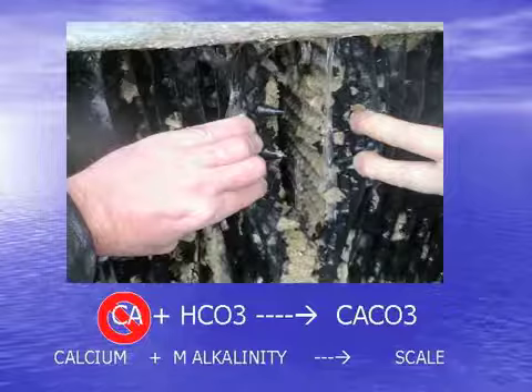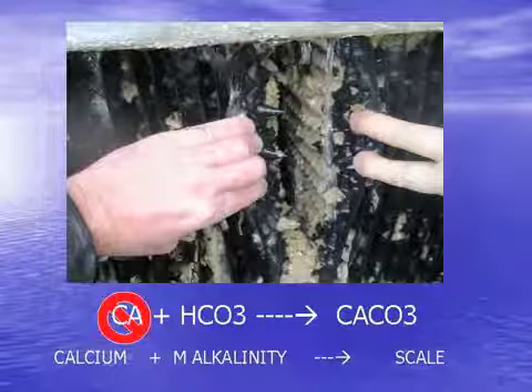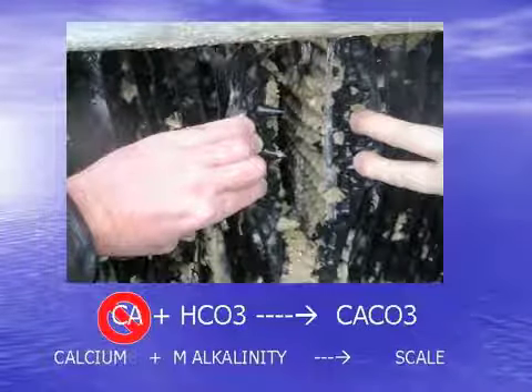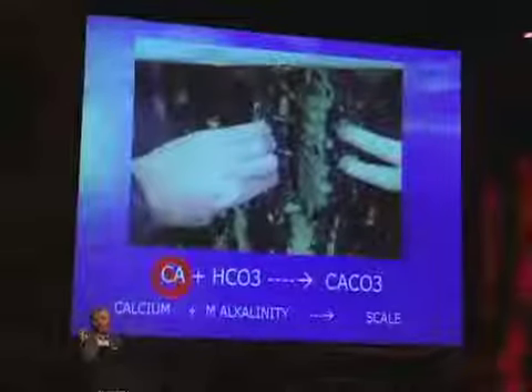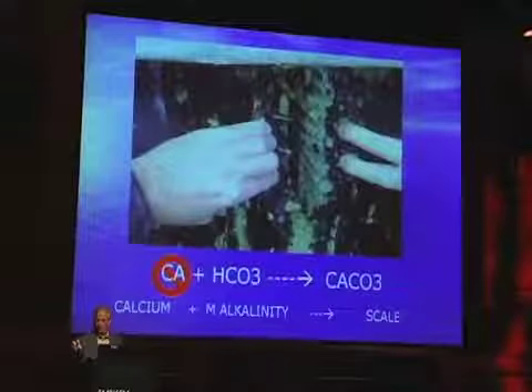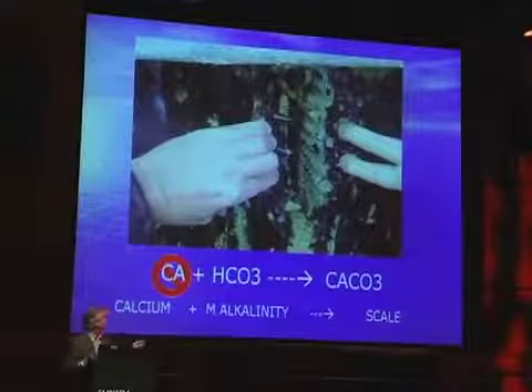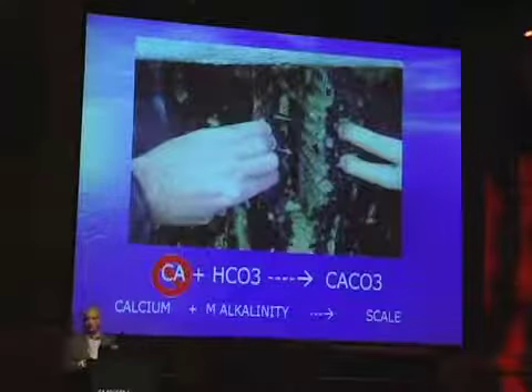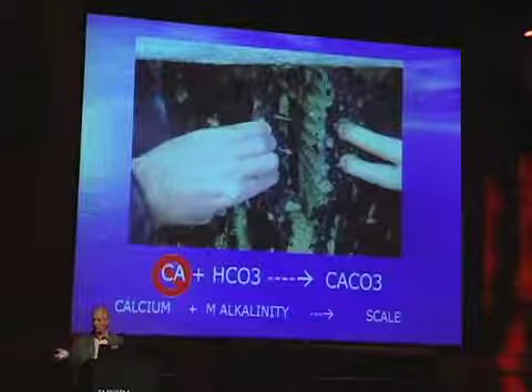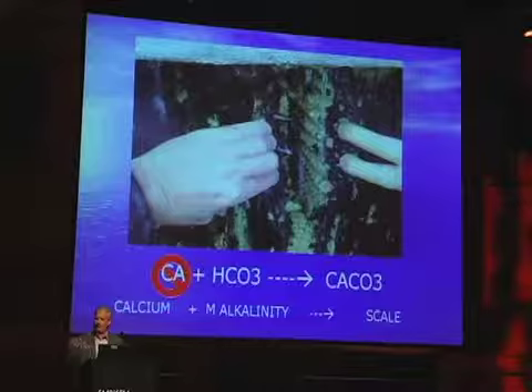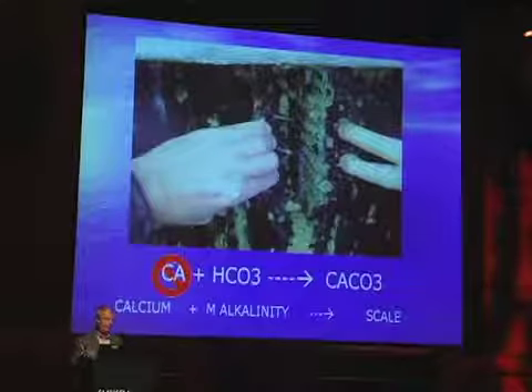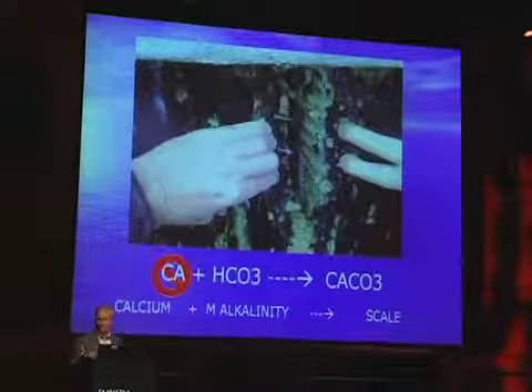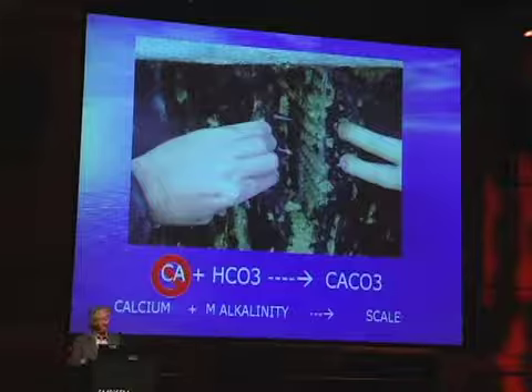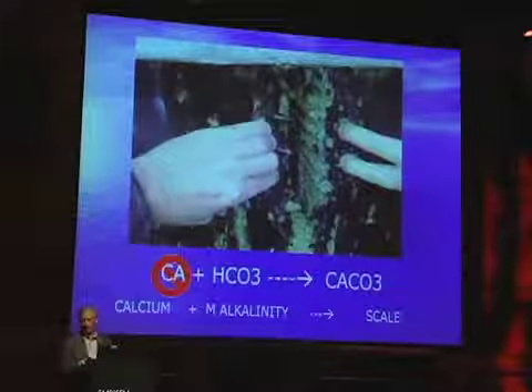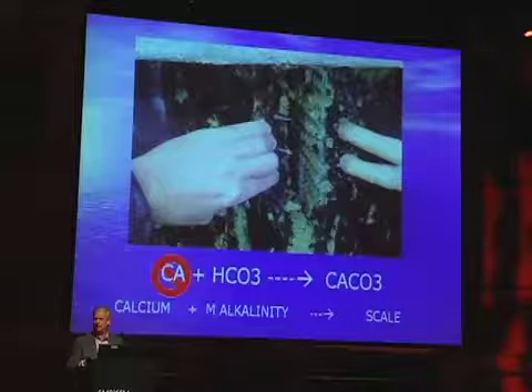Or you lose control of the softeners, or something happens to them. You have to remember, the water quality has been void of calcium because you've been softening the water, so alkalinity is sitting there waiting, building up because you're cycling it out. If those softeners fail and you suddenly introduce calcium into the water, that water is primed for it, and immediately you'll start scaling the cooling towers, within a couple of days.